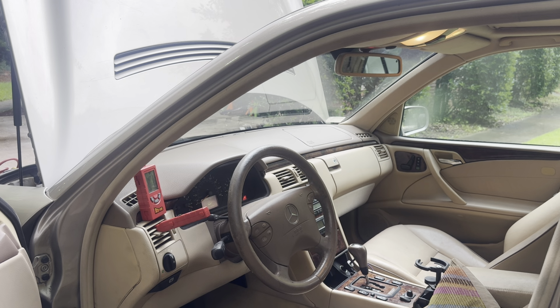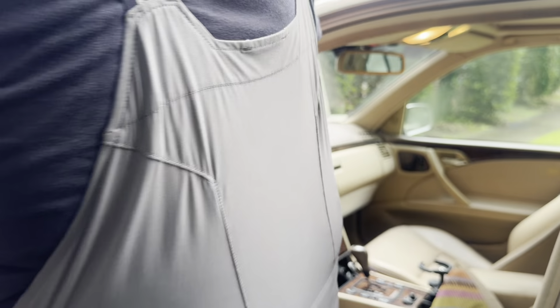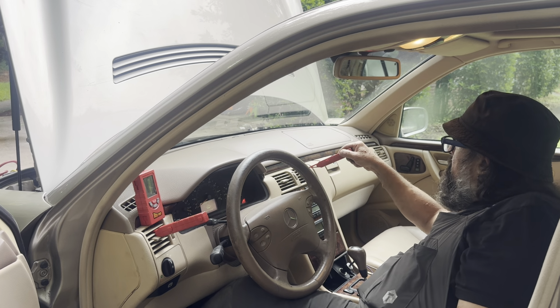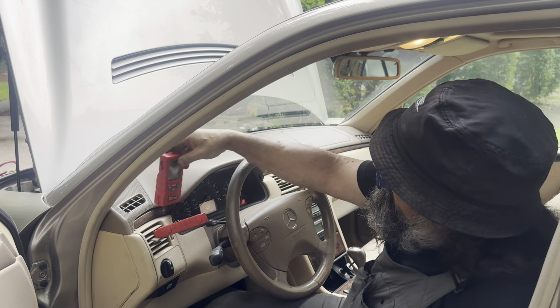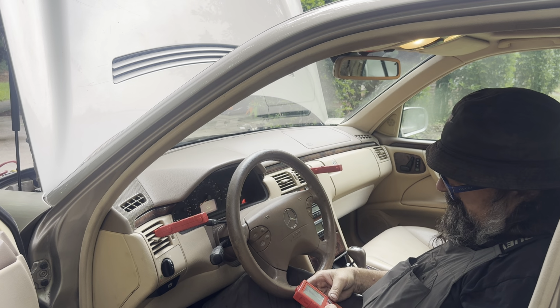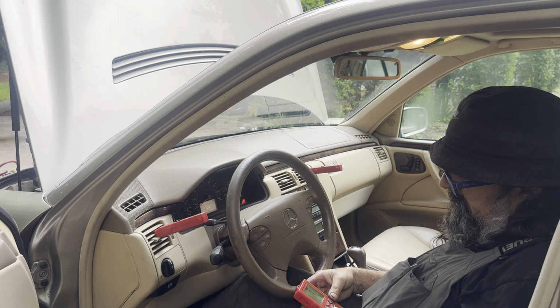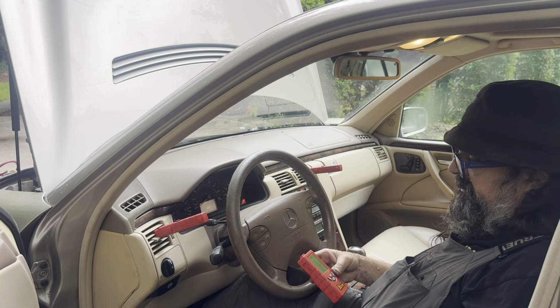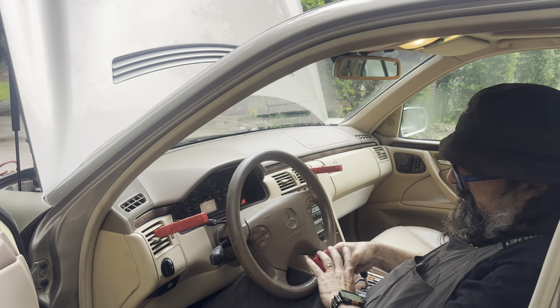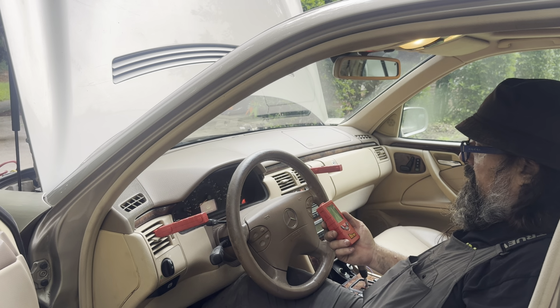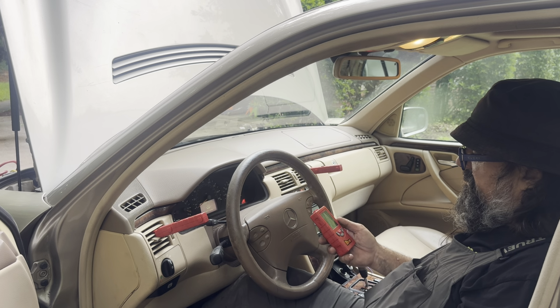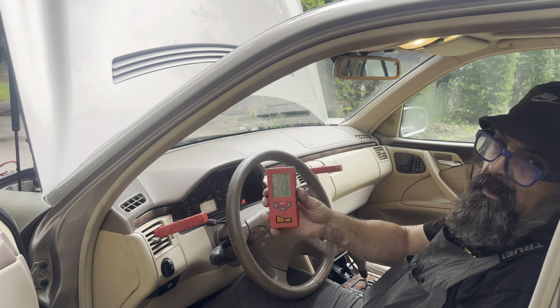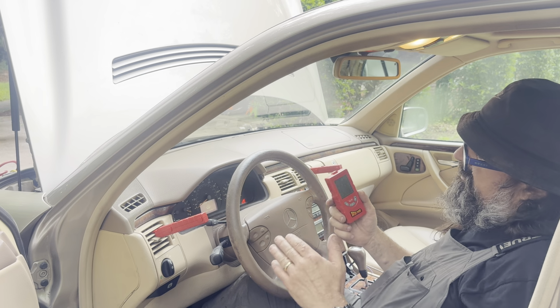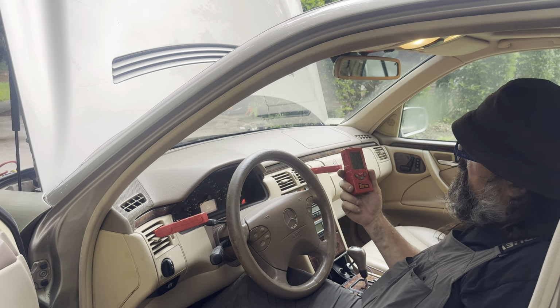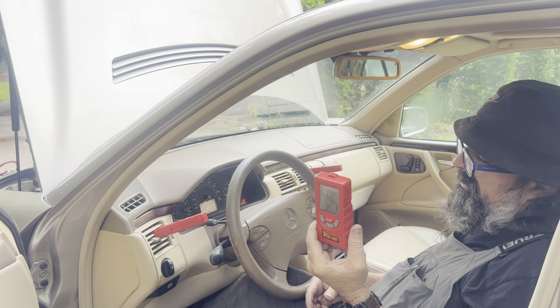Alright, so right now our pressures are 30 and 200. We got our secondary probe here. Those probes are on. We're going to put one here in the middle. Right now the outside temperature is 76.5 degrees, which tracks. This one is blowing at 56, and this one over here is at 55. So if you're working on AC and trying to determine if you're pretty equal across the board for your temperatures, this little power probe temperature unit is one of the best things you'll ever have.